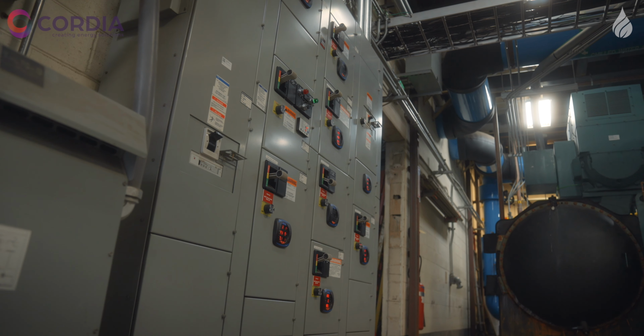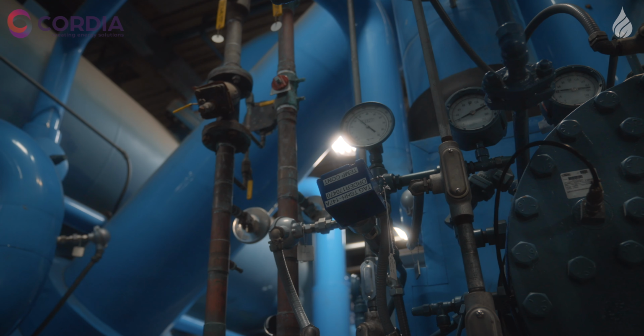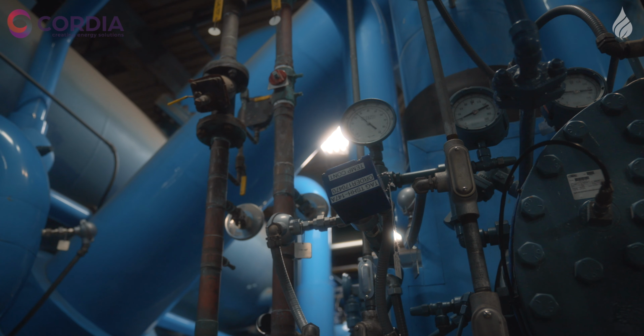Any drawbacks associated with the program? The only drawback I have is during the wintertime, during low load operations, when I don't have a lot of air blowing through the towers, I tend to get drift, which causes a small salt buildup on the inlet louvers. If we go up and wash them once a month, it comes right off, just using a makeup water hose to wash the inlet louvers. So that's the only drawback I have, and it's only during wintertime during light loads.